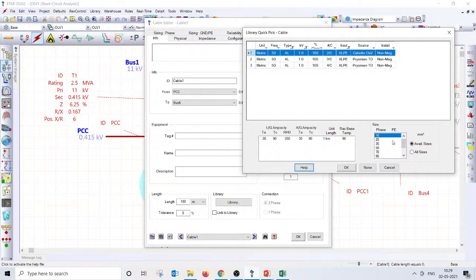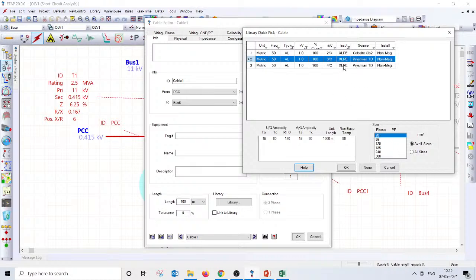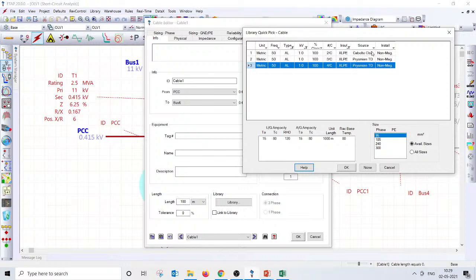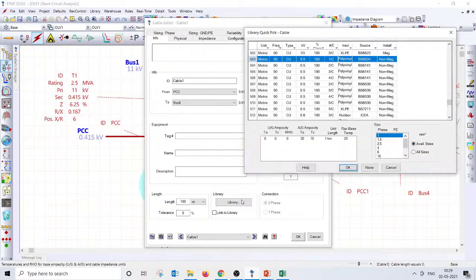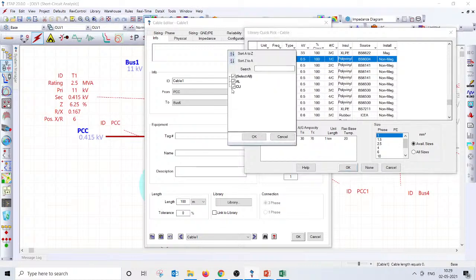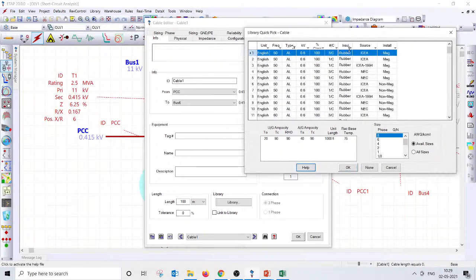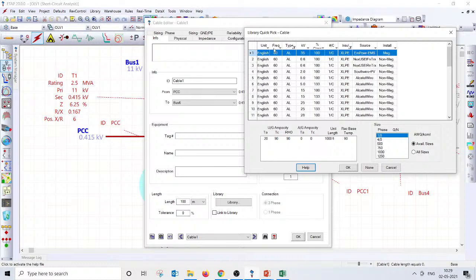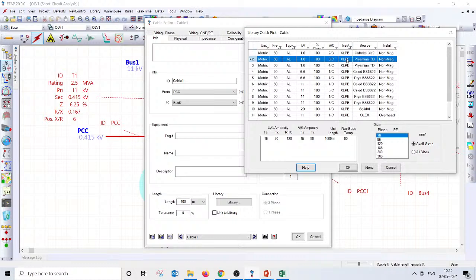and guess what, if you go with the 3 core, the minimum cable size itself is not really, that means you don't have the correct library there, right? You can probably even take a very small size which can carry just 7 amps, which is more than sufficient. So let's not really focus on the voltage then. Let's choose the conductor alone with an insulation of XLPE. Logically it makes sense. Single core cable definitely you need not go. Frequency anyway 50 hertz is what we are using, right? Let's look at what could be the minimum size of the cable which we have.